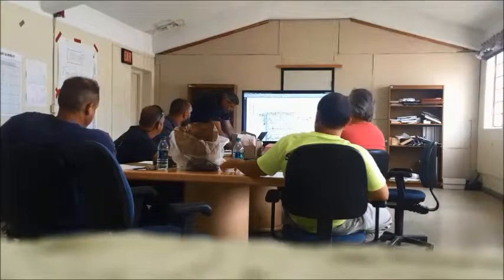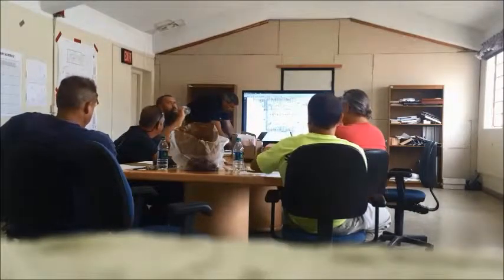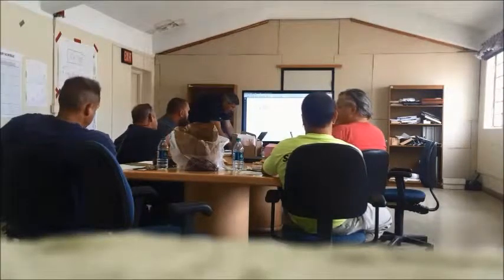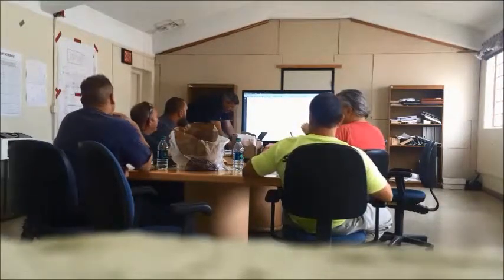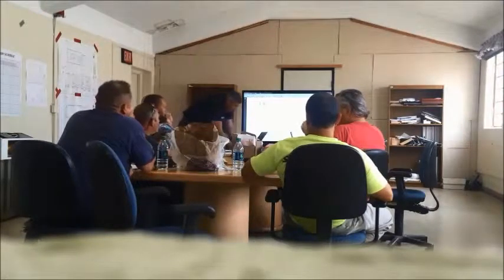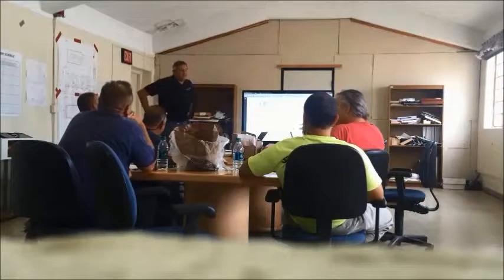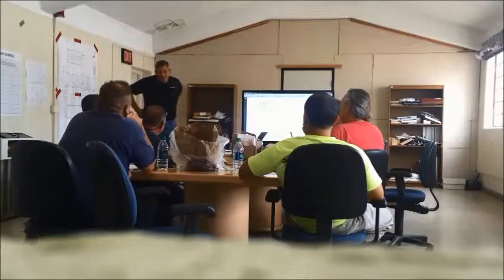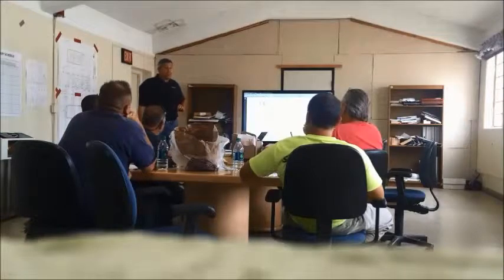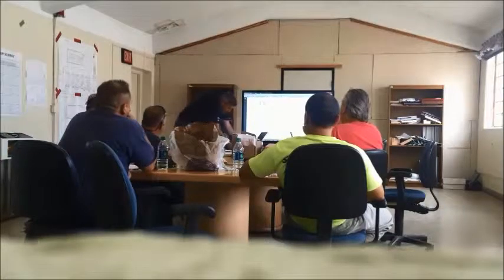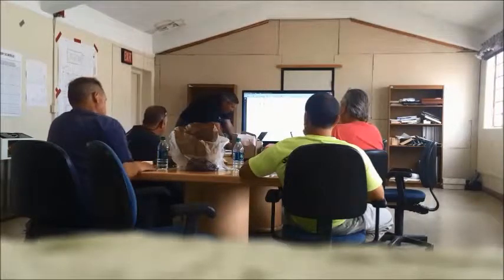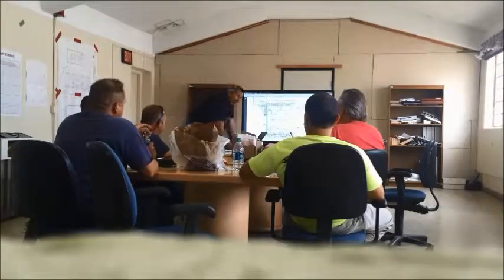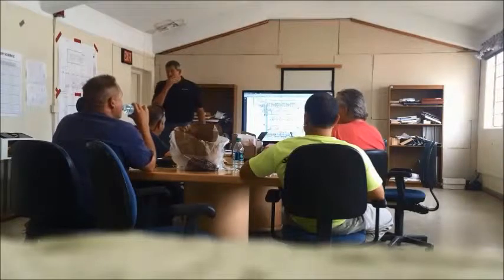Chilled beam wise, basically they're all the same chilled beam. There's a heating connection and a cooling connection on all of them. It's just that we didn't hook up the heating connection on the interiors based on design. Good, those are the ones that leak. Oh, they do? On these projects, yeah. Sharp fitting on the flex hose, and it leaks every time. You talked about that when I first got here, there's something about it, right?